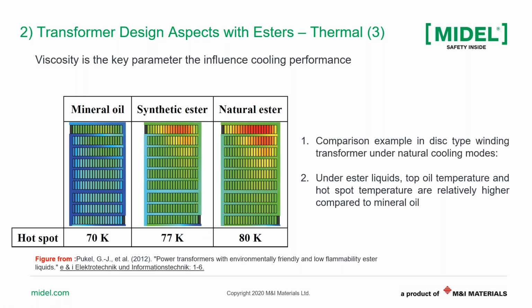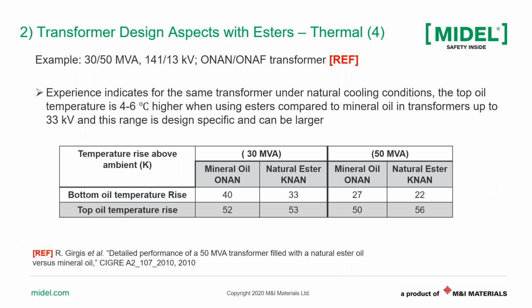So this is one example, and the other example is really a practical one. Here the researcher retrofilled a 30/50 MVA transformer, 141 kV, 13 secondary, and then measured the top liquid temperature and the bottom liquid temperature. These temperature values of that experiment are shown in the table. So let's focus now on the table. You look at the first column, the temperature rise above ambient. The first row is the bottom oil temperature rise, and then the top oil temperature rise.